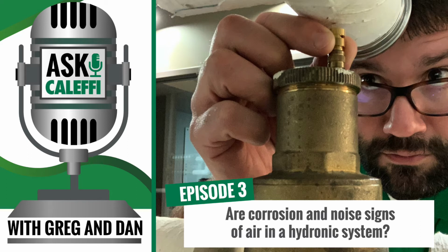Yeah. So last week we talked about air vents, Greg. What's the major difference between a separator and an air vent? That's a good question, because the terminology is misused a lot, I feel. It is. We'll get somebody who calls in and says, I got an air vent, or I had a guy calling an air vent an air separator a lot. And I had to kind of reel him in and say, look, this is the difference between the two. You can't confuse the two. They're different. They do the same thing, where they remove air from a system. Right. Air removal, whether it's an air vent or air separator, is why they're in the system.